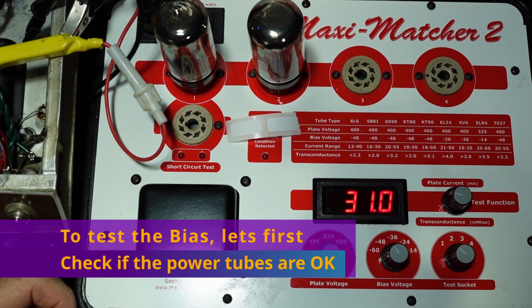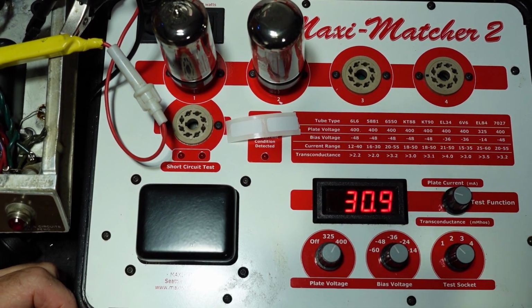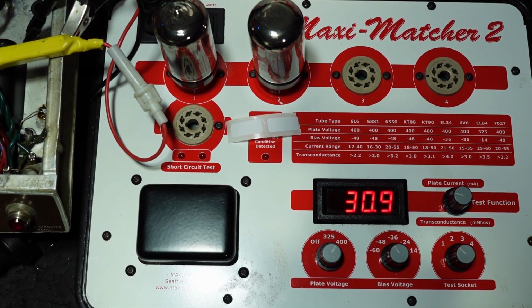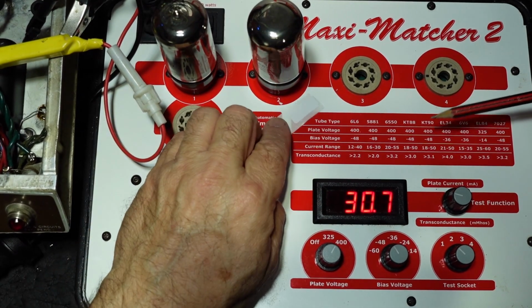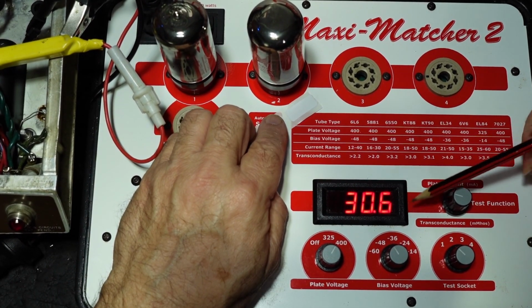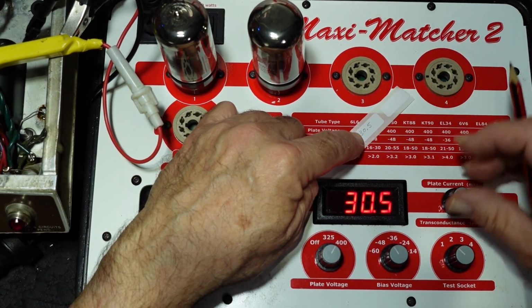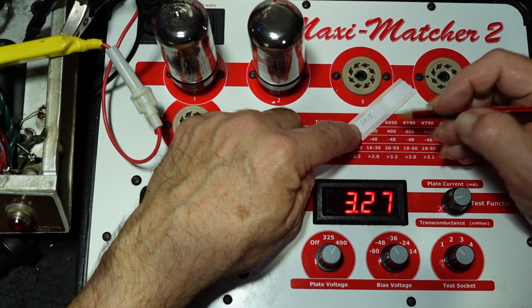Alright, I'm now testing the owner's original tubes. I'm hoping they are okay. We're going to be measuring plate current and transconductance for the 6L6. We'd like to see over 12 and under 40, and that one's looking pretty good. This is valve number 1, so we'll call that a plate current of 30.5 milliamps. And for transconductance, we want over 2.2, which it is, so that's 3,270.